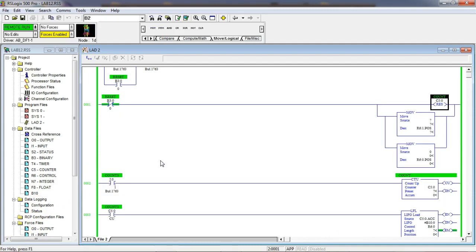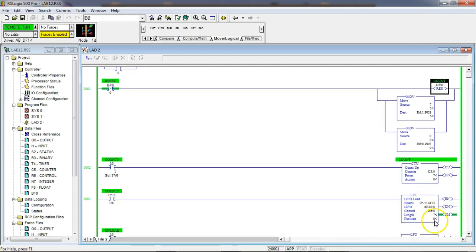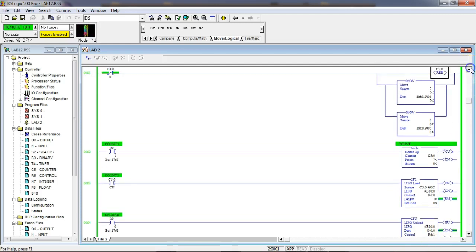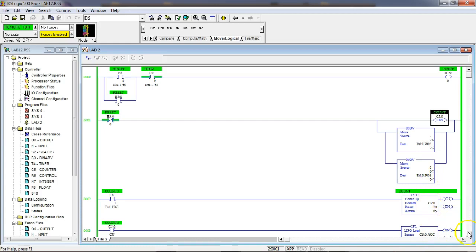I thought I should show you how we can automatically load our last in first out stack position with zero and automatically load the unload or pop instruction with seven, so we can reuse this over and over. Notice what I did in my master reset circuit — I put a move instruction. This resets my counter, and this move automatically puts 7 into the position register for our pull instruction, and moves 0 into the position register for our push instruction.